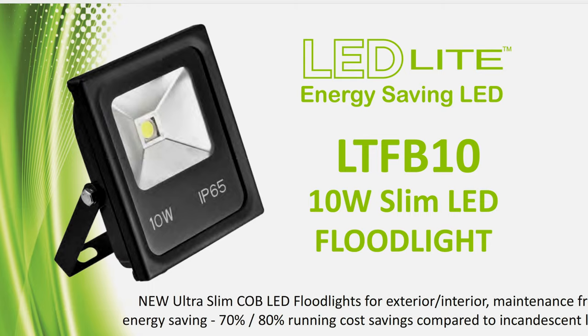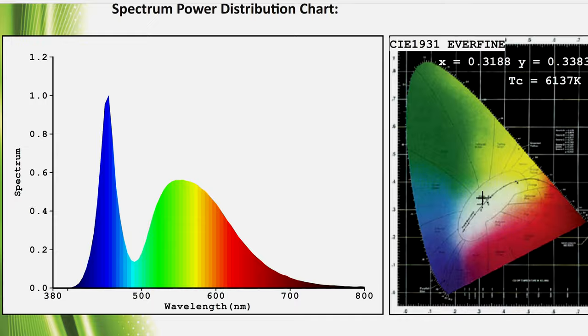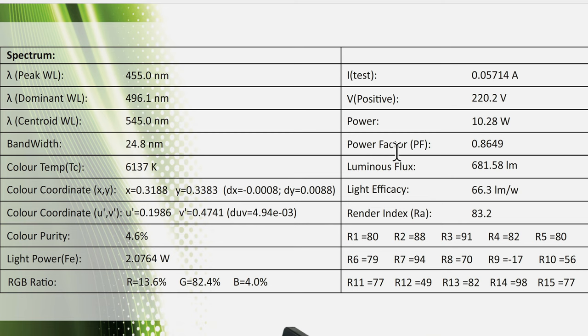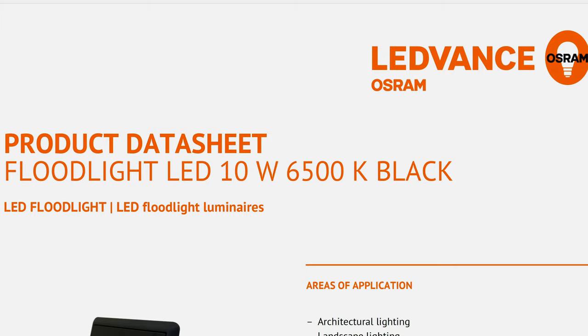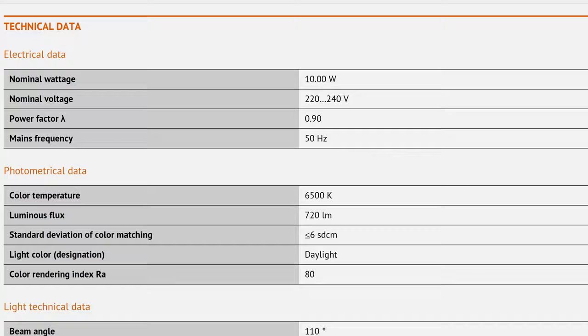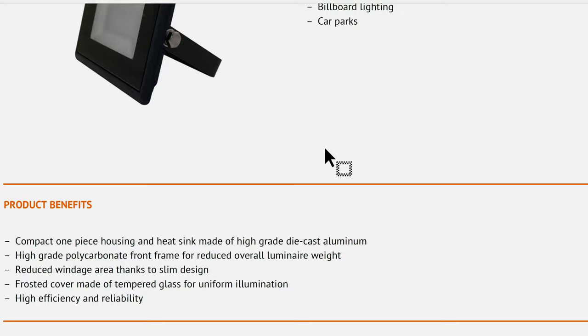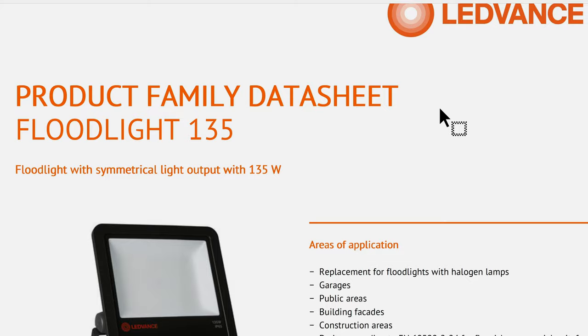Looking at some datasheets for floodlights — if I scroll down we have the specifications, but notice it doesn't give the inrush current. It just says power: 10.28 watts, and may include the power factor, but no inrush current. Looking at one from Osram, it just says 10 watts with no other values to help determine the inrush current or how many floodlights could connect to one circuit breaker.